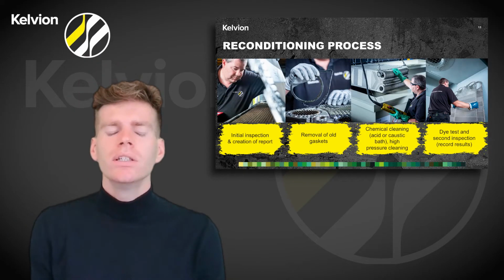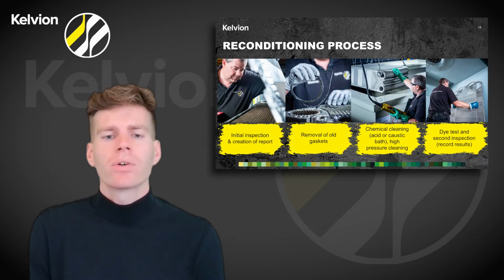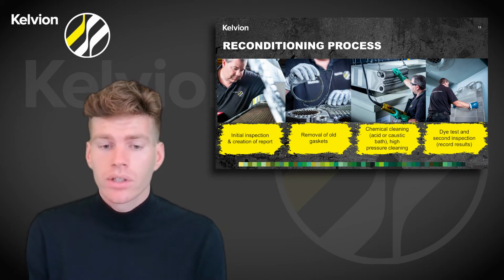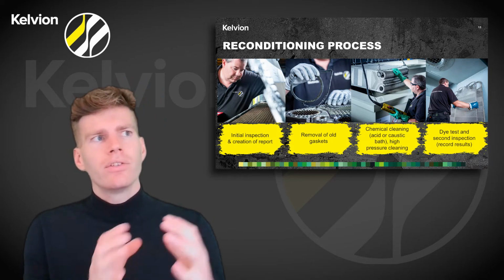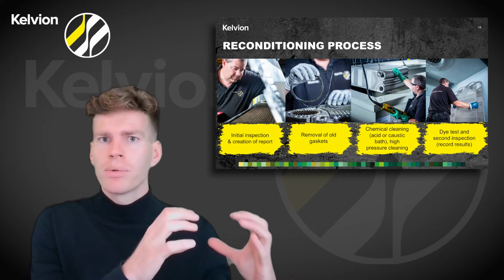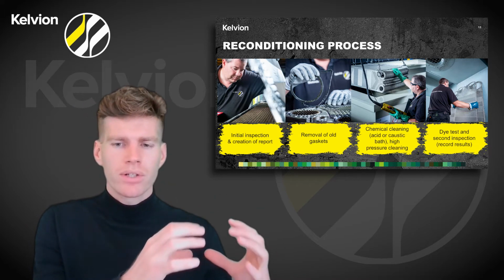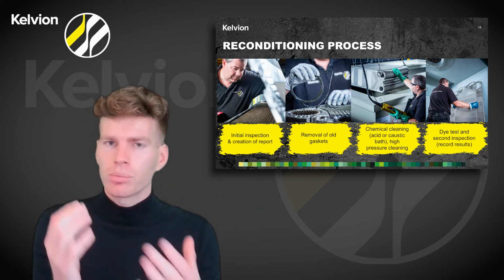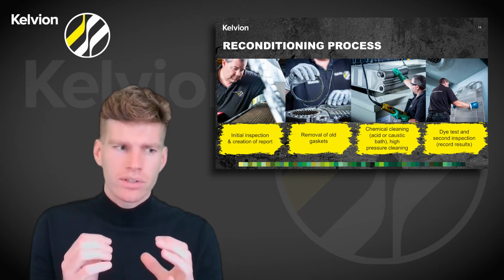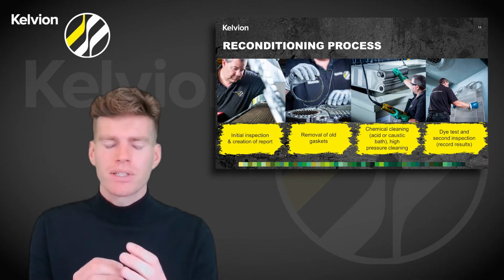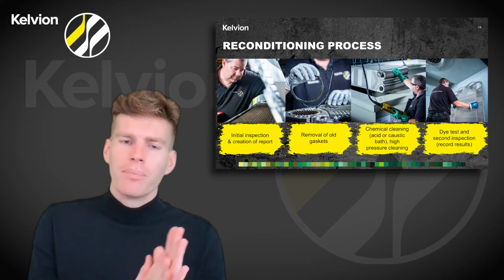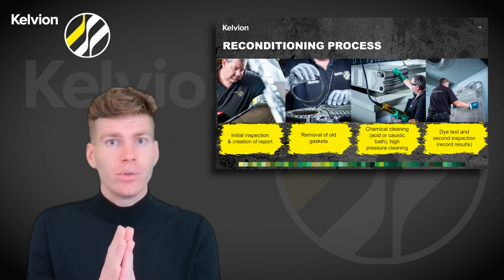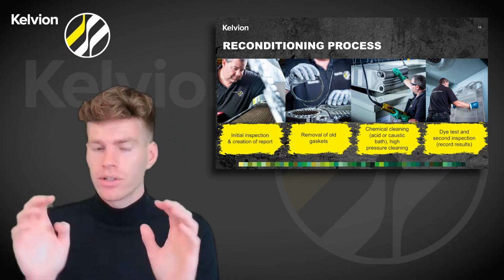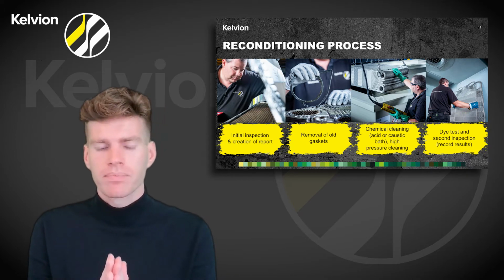The second service we want to focus on is the reconditioning service. Let's assume that during the performance audit, one conclusion was that one heat exchanger in your process was not performing according to specification. The recommendation was to clean the unit via our proven 10-step approach.